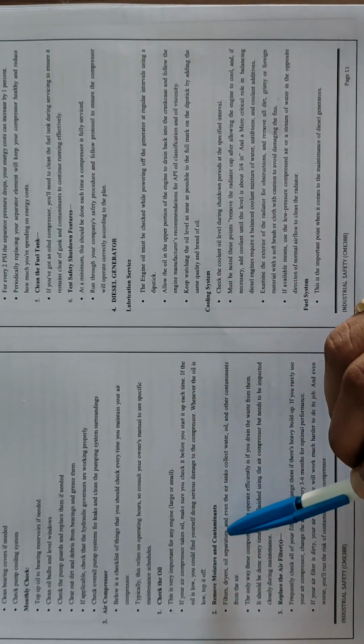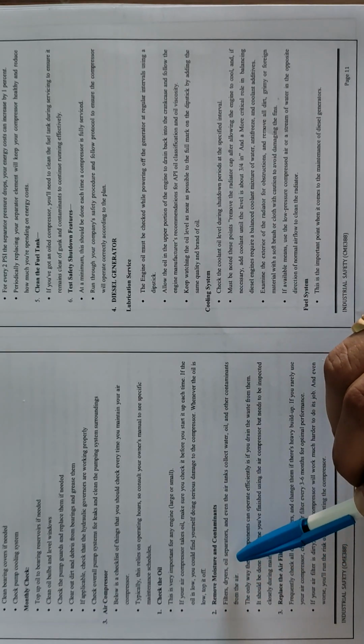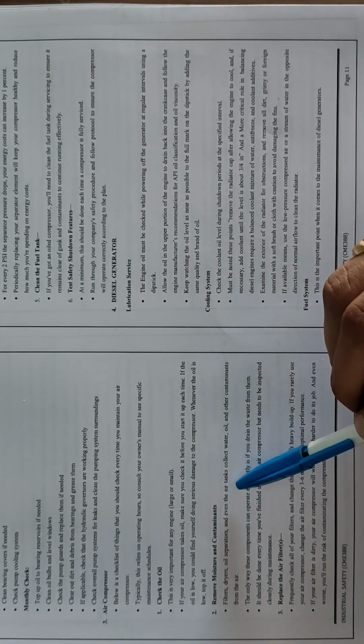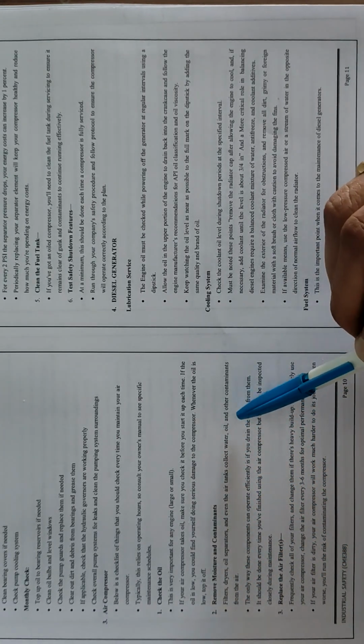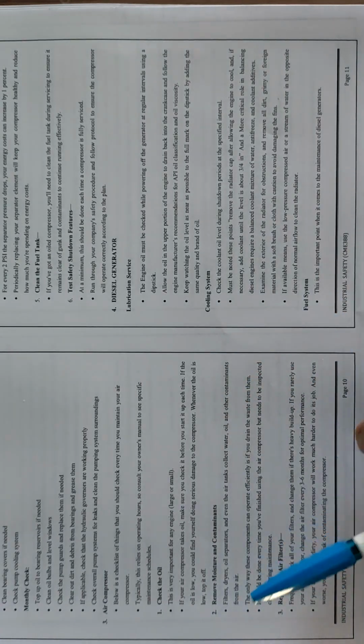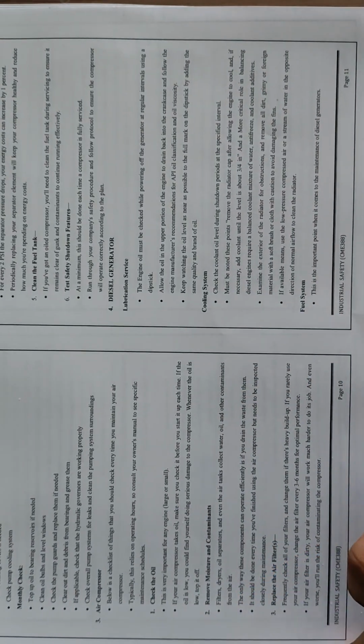Remove moisture and contaminants. Filters, dryers, oil separators, and even the air tanks collect water, oil, and other contaminants from the air. The only way these components can operate effectively is if you drain the waste from them. It should be done every time you have finished using the air compressor, but needs to be inspected closely during maintenance.